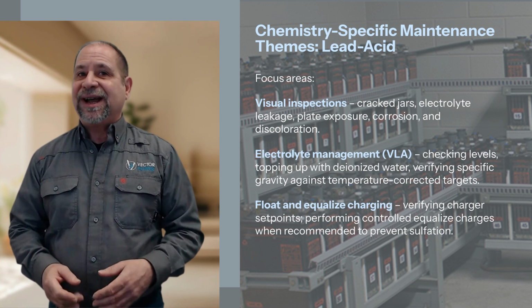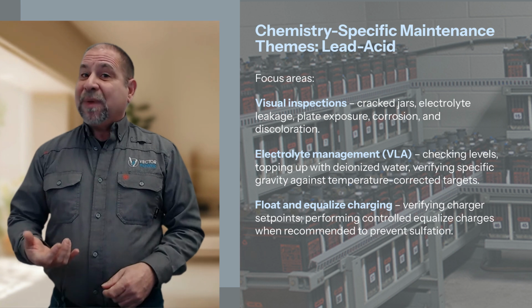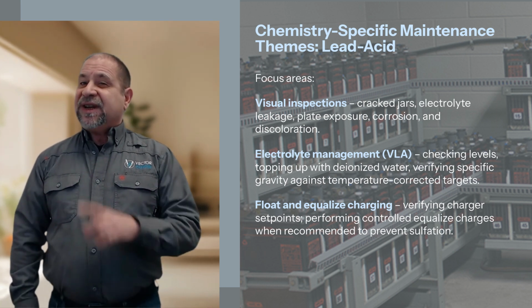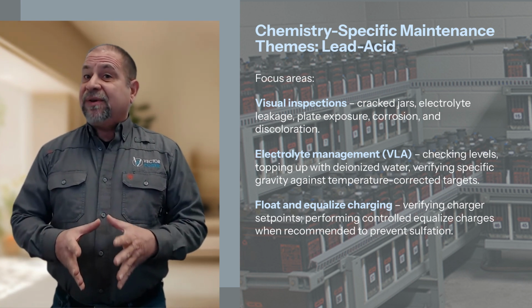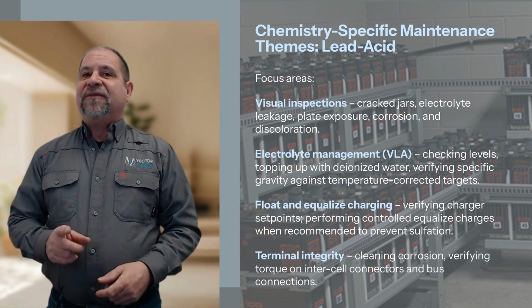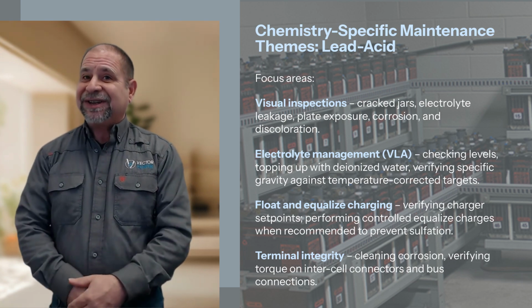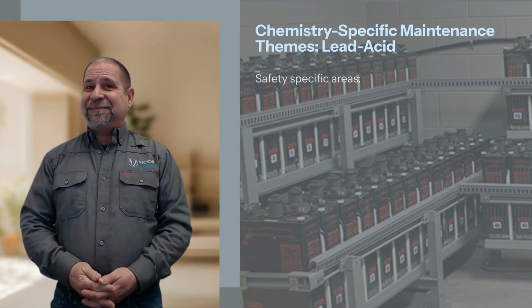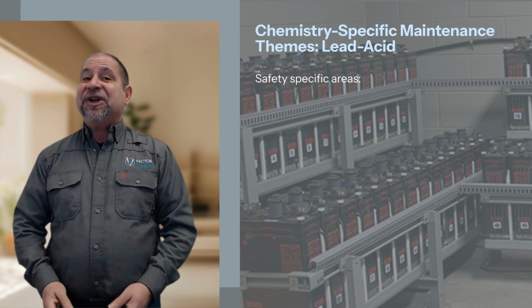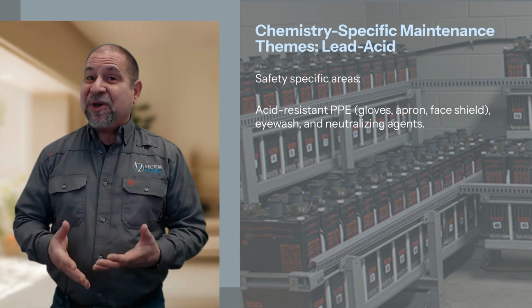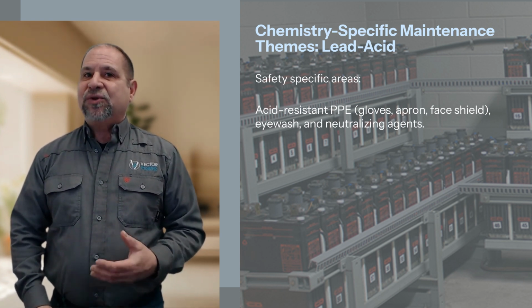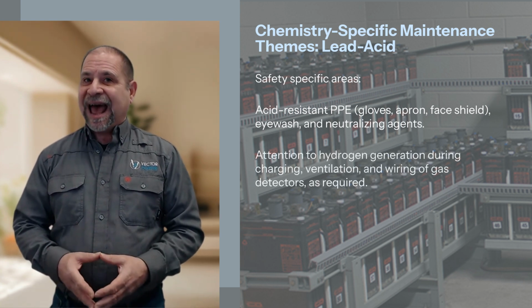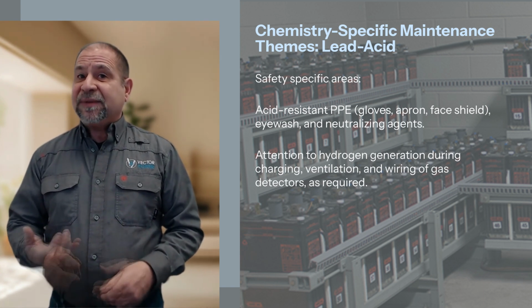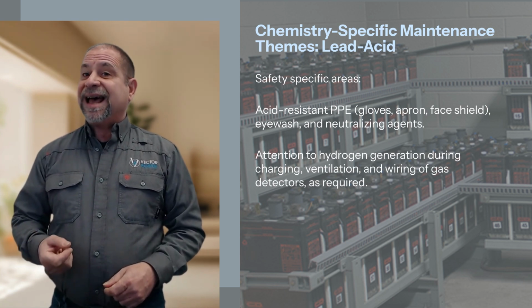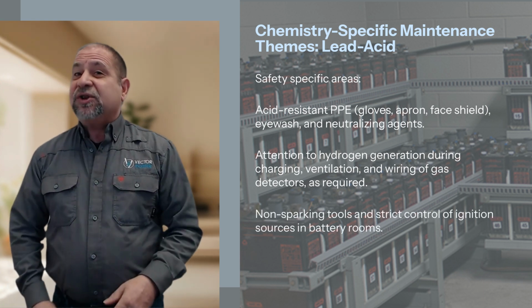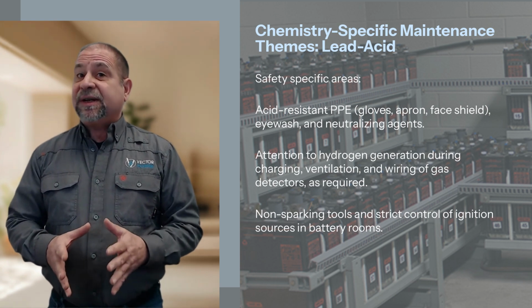Float and equalize charging. Verifying charger set points. Performing controlled equalize charges when recommended to prevent sulfation. And terminal integrity. Cleaning corrosion, verifying torque on inter-cell connectors and bus connections. Safety-specific areas of focus. The use of acid-resistant PPE: gloves, apron and face shield, eye wash, and neutralizing agents. Attention to hydrogen generation during charging, ventilation, and wiring of gas detectors as required. And the use of non-sparking tools and strict control of ignition sources in battery rooms.